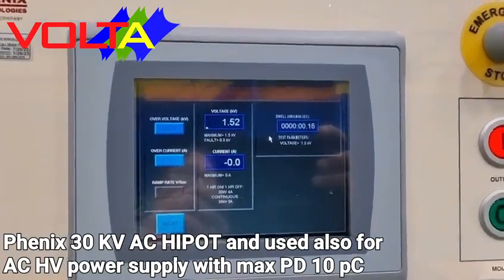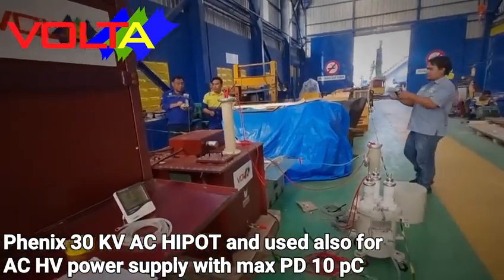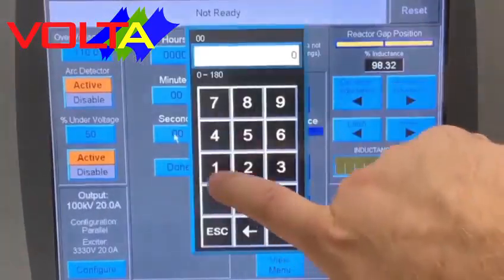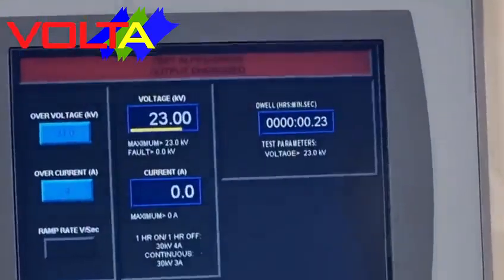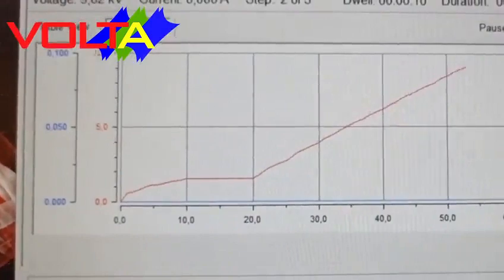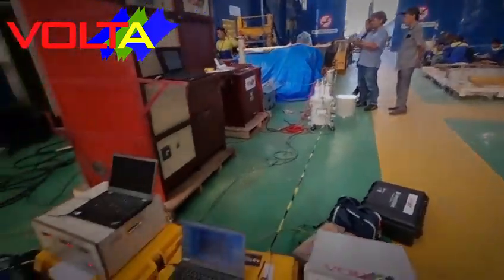For PD-free high voltage power supply — to perform partial discharge and tangent delta tests for large size generators with voltage more than 12 kilovolts — we use the Phenix type 6TC 125-30 with fully computerized control. Our Phenix high voltage power supply has very low PD, with maximum PD of 10 pC. The Phenix 6TC is mainly an AC fully computerized auto hi-pot with individual dwell time and ramp voltage.